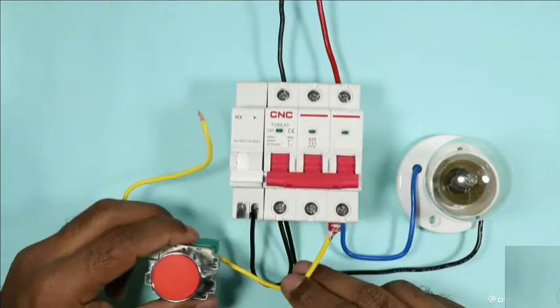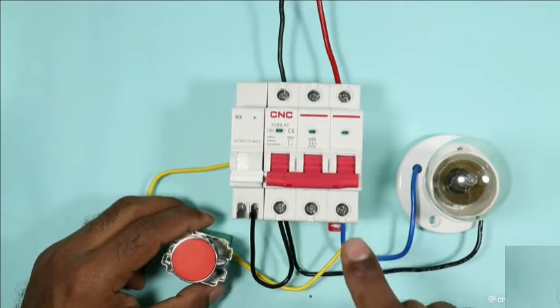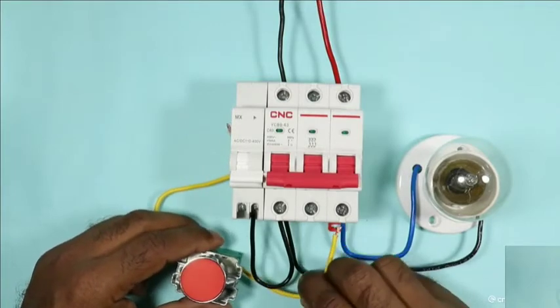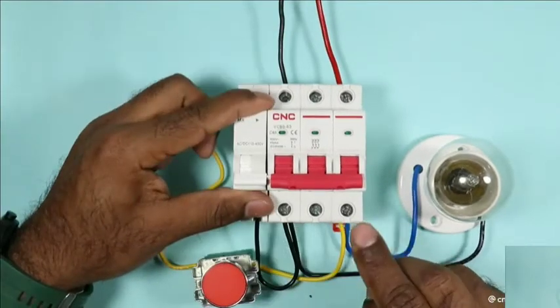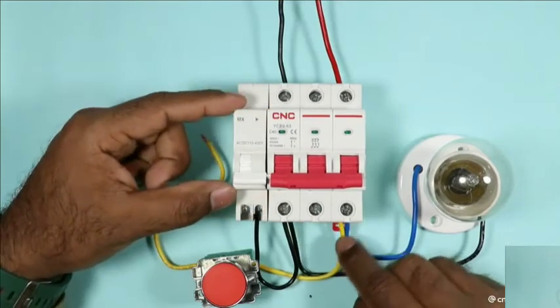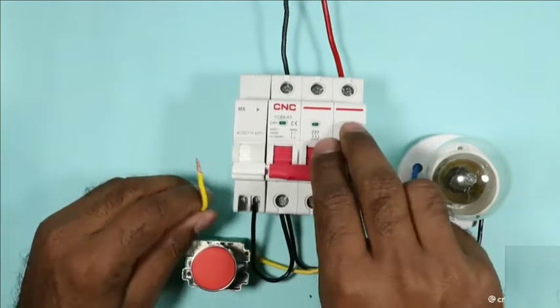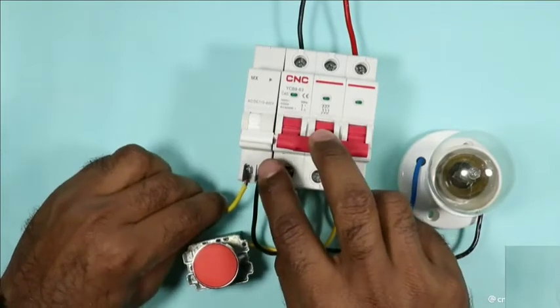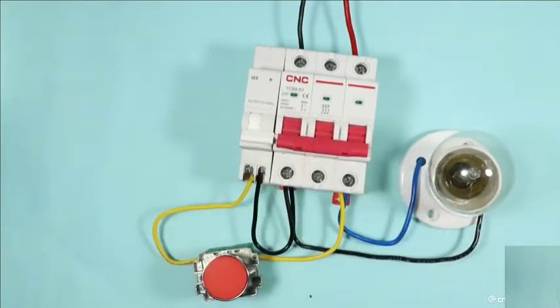Connect one wire of this push button with output terminal of MCB where we get phase supply. In this terminal I receive phase supply, so I connected wire here. This second wire of push button is to be connected with second terminal of shunt coil. This much connection is only required.